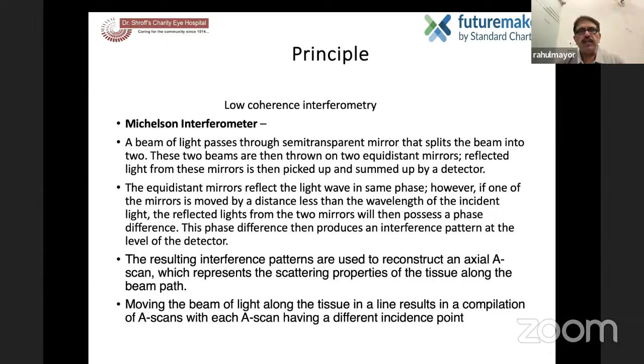So I'll directly go to the principle. Basically, light from an OCT system is broken into 2 arms: the sample arm, which is the item of interest, and the reference arm, which is usually the mirror. The combination of the reflected light from the sample arm and the reference arm gives rise to the interference pattern, but only if light from both the arms has traveled the same optical distance. That is, the difference is less than the coherence length. So then only we can acquire this.